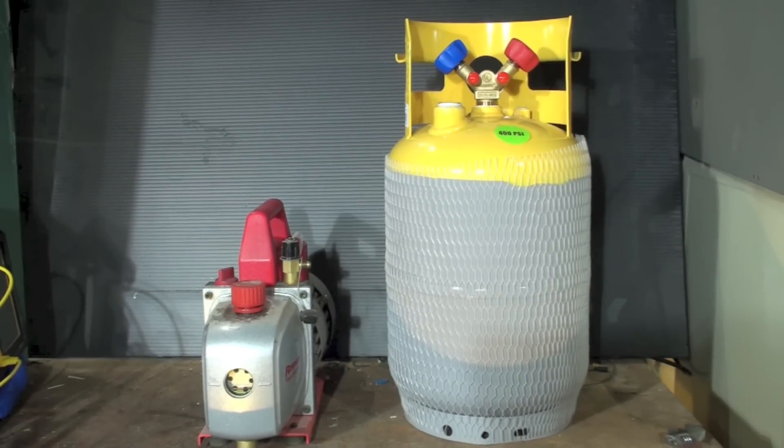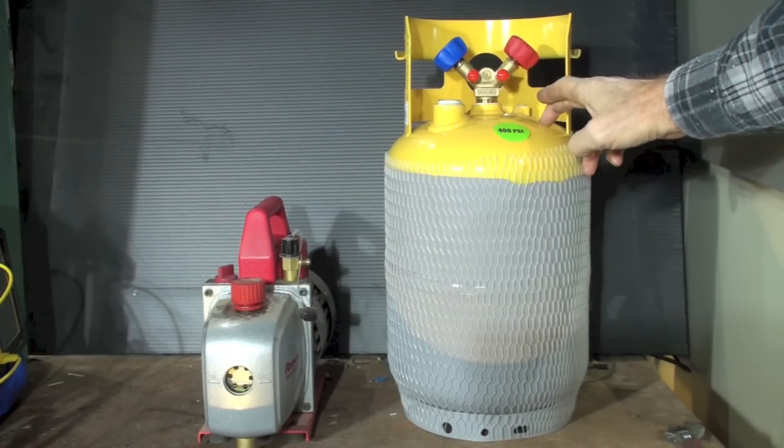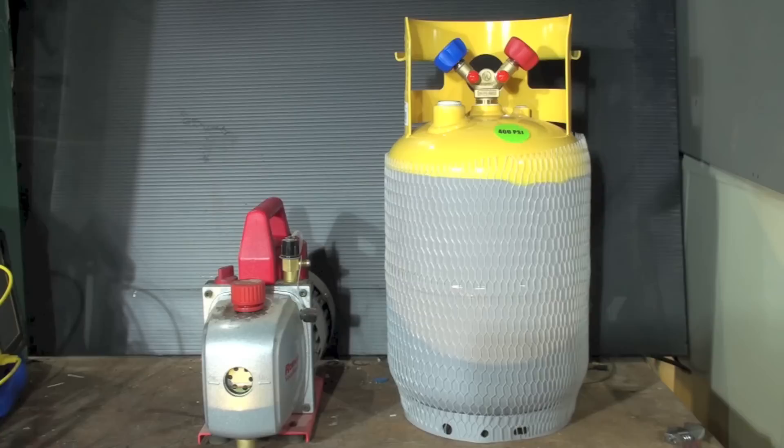Okay, here we have a brand new recovery cylinder. Virtually all the recovery cylinders anymore are the 400 PSI, good for R410A. I'm going to go through the procedures we use when we get a new one. Some of you guys will think I'm being excessively picky about some of the things I do with these recovery cylinders. I'll teach you the best way I know, then you can screw it up out in the field if you want.